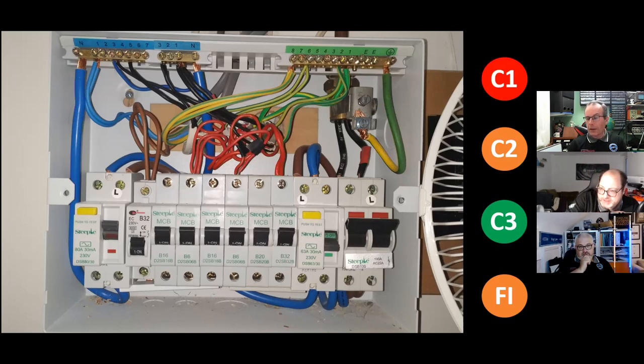So in theory, it's all Denmans, but looking underneath it, you can see the busbar. There's clearly not enough clearance there. Yeah, that breaker does not like that board. No, it doesn't. It's been bodged in, swarfing the board, naughty boys. The line conductors just look like a bit of a twisted mess.